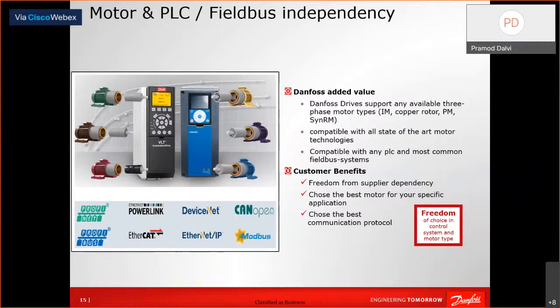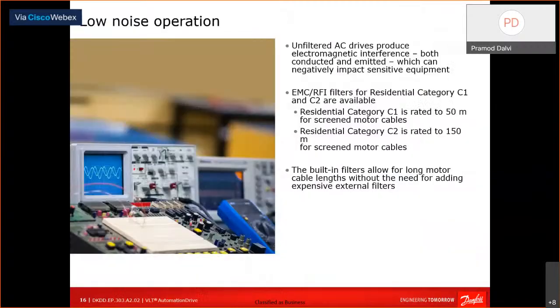As well, you can connect these drives to any motor. Like today it is an induction motor, but tomorrow if you want to change to a synchronous motor or copper rotor motor, this is possible. You don't need to change the drive. The only thing you have to do is change a few parameters. That's it. So this is where we are motor and field bus independent. We can connect to any motor and any field bus.